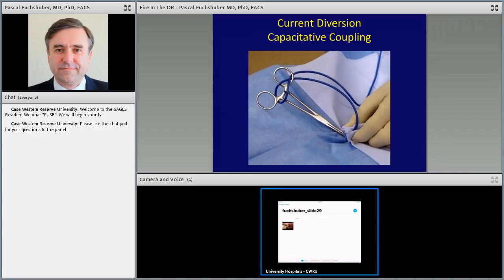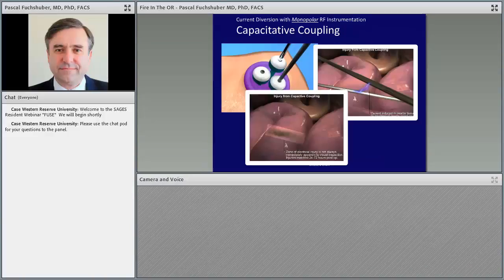Another very common situation where you have capacitive coupling is when you do this, which is very common. I would venture that half the operating rooms I walk in today in the United States will have a situation like that. This is capacitive coupling. The energy that goes through the cord that's insulated jumps onto the clamp, and if the clamp for some reason touches the skin of the patient, there is a risk for burning the patient's skin. So you should never do that. You should really use the holster.